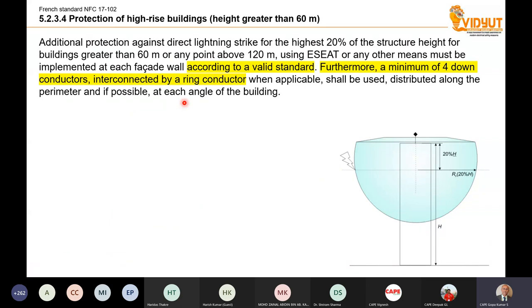The French standard also says that if you have a high-rise building, you have to have additional protection against direct lightning strike for the top 20% of the structure above 60 meters. So that means for tall high-rise buildings, the top 20% has to have this, or any other means must be implemented at each facade, if you have a facade on the building, according to a valid standard. Actually, this is very clever wording. The only valid standard is the IEC 62305. What the NFC standard says is that for a high-rise building, you make an equipotential bonding or a connection according to a valid standard, which is the IEC standard. Furthermore, a minimum of 4 down conductors interconnected by a ring conductor, when applicable, shall be used. Unfortunately, these are not done in India.